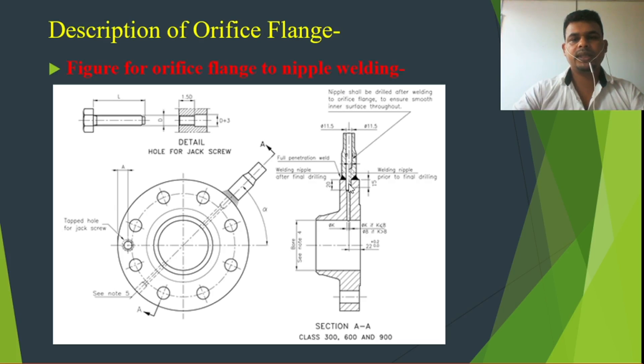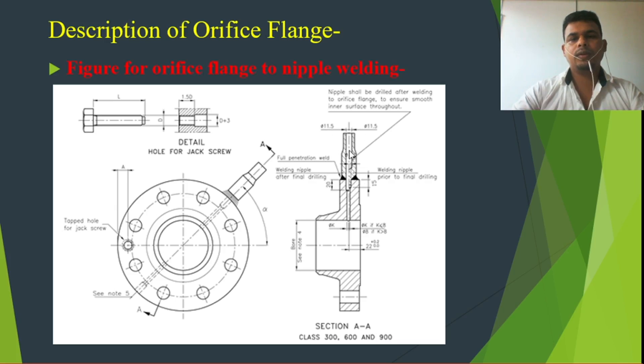The nipple shall be drilled after welding to ensure a smooth inner surface throughout. We need to ensure the inner surface is smooth to get the correct flow reading. This is the welding requirement for the nipple connection on orifice flanges.